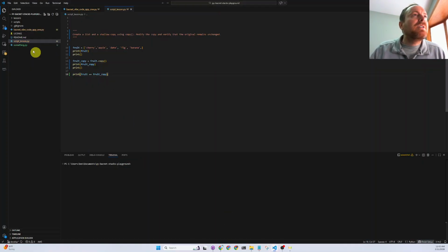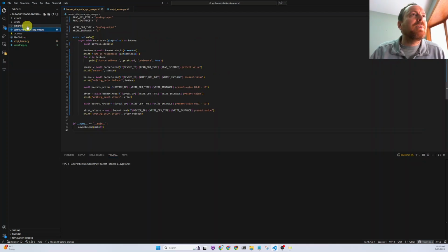Okay, so this was our vibe code app 1. These were all of our single read and write features, and we also did a Who-Is right here. To do all of this, reference the earlier videos, but this is basically the end product. We had two writes: a write of the present value of 88 at priority 10, and then we released that priority 10 override on our BACnet device and checked it with our BACnet scanner tool from the older videos. Then we read the values just to make sure they took.